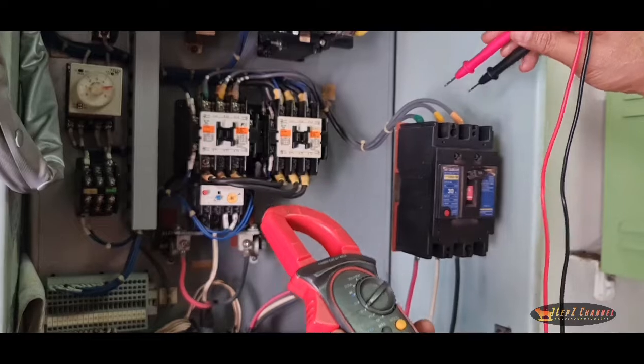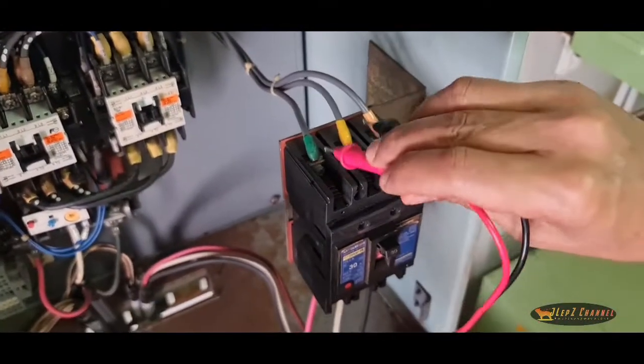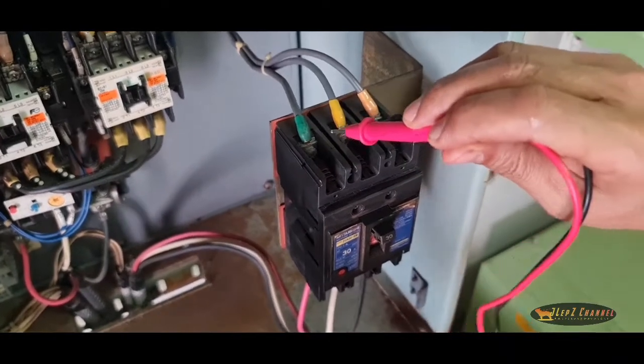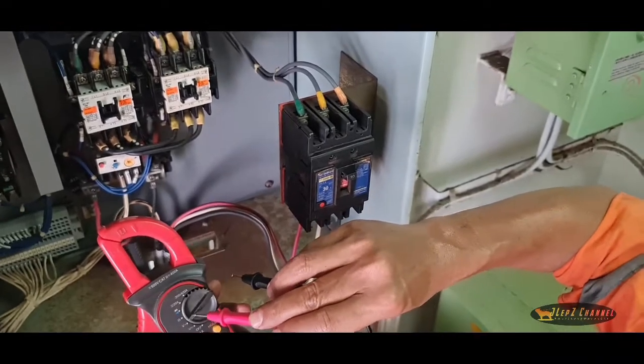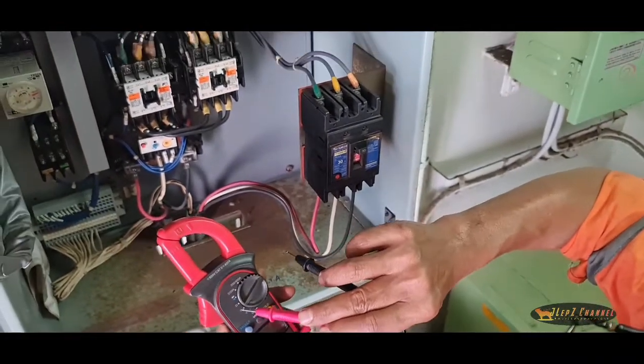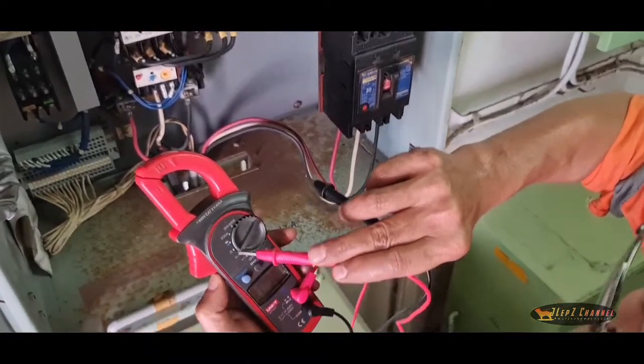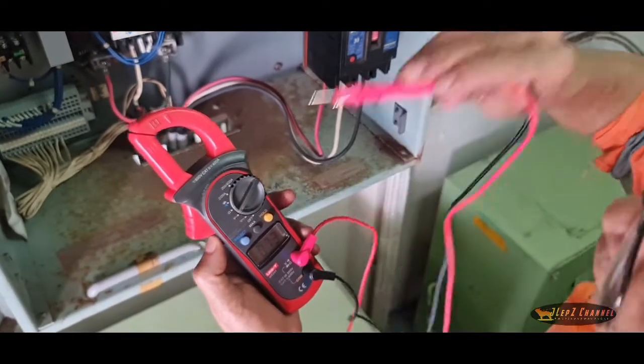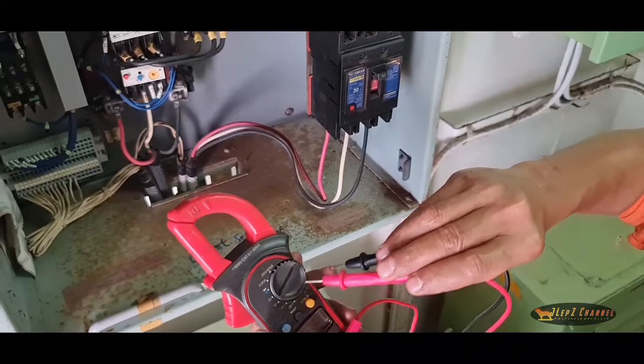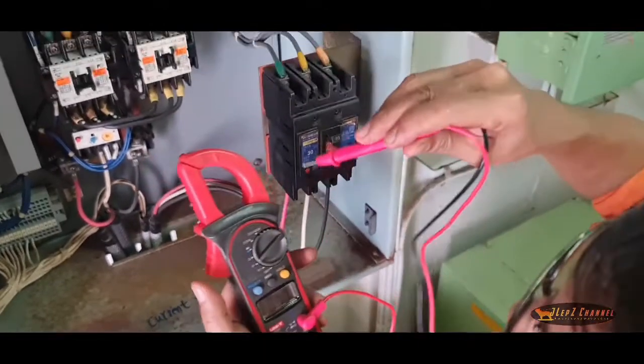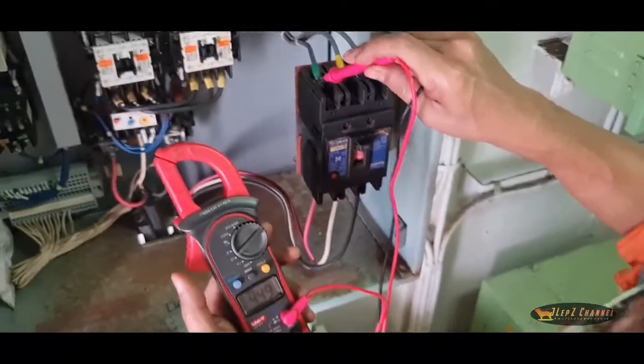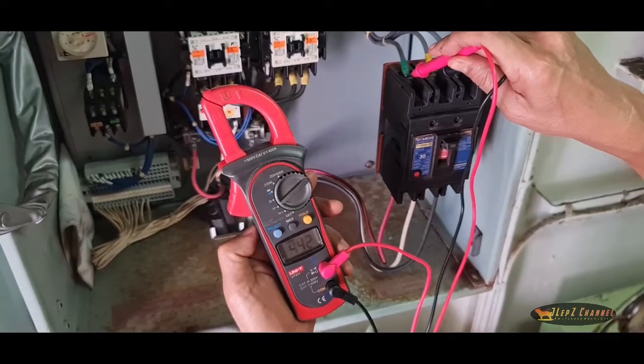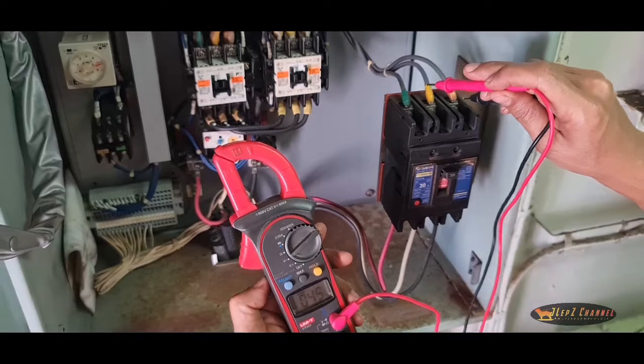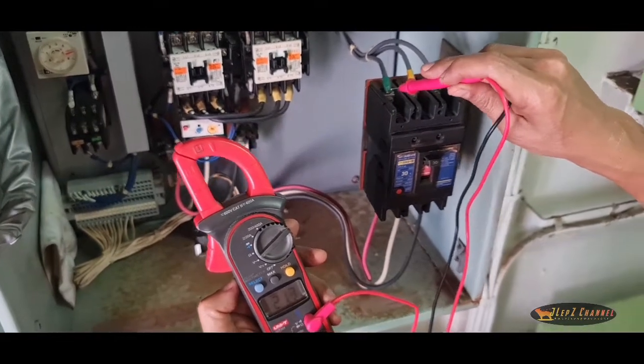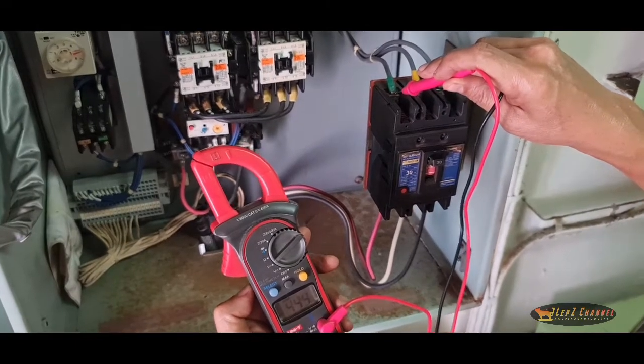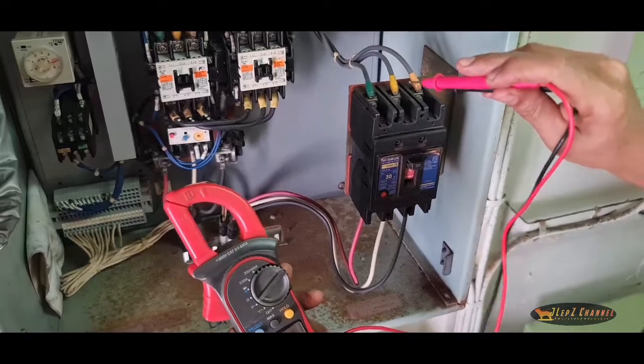If you want to test the voltage, this is line 1, line 2, line 3. Since we already pointed the selector to alternating current voltage, just remember that the wave is the symbol of alternating current. The direct current is used for testing battery voltage. Now we will test the voltage. You see, line 1 to line 2 voltage is 443. Now we will test line 1 and line 3, the other side, with the black on the right side and the red on the left side. Now our reading is 444. There is a difference of 1 volt, but that is negligible.